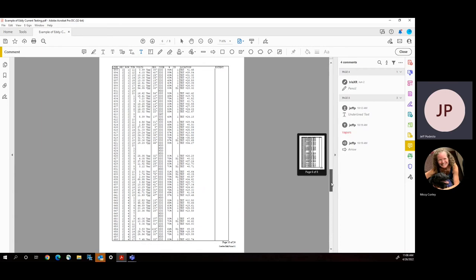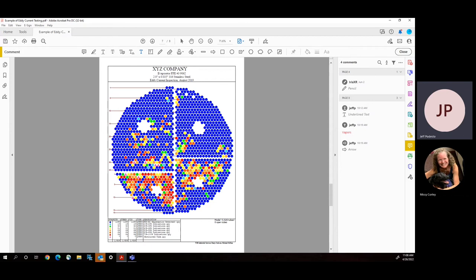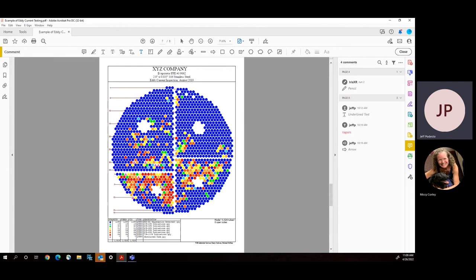In this case, those last two charts would be converted to what we have here, which is another scorecard that relates to the two tests that we just showed you. And this is the third effect, and there are four of an evaporator system, and in this case, there's four passes in this third effect, the lowest concentration leading all the way around to the highest concentration, which is in this lower left-hand corner. And what we begin to see is that most of the failure is happening in the higher concentrations, and from the data, we know that that failure is along the whole length of the tubes. And from that, we can tell that we've got a corrosion issue probably happening, we're fairly sure, and we know that the product has a salt content in it, and at a higher concentration, that can have negative effects on the materials of construction of these tubes.